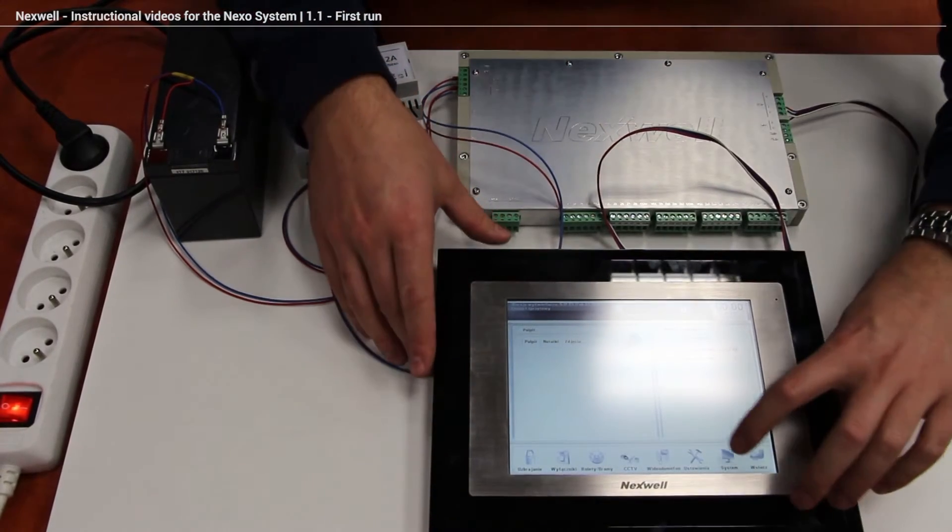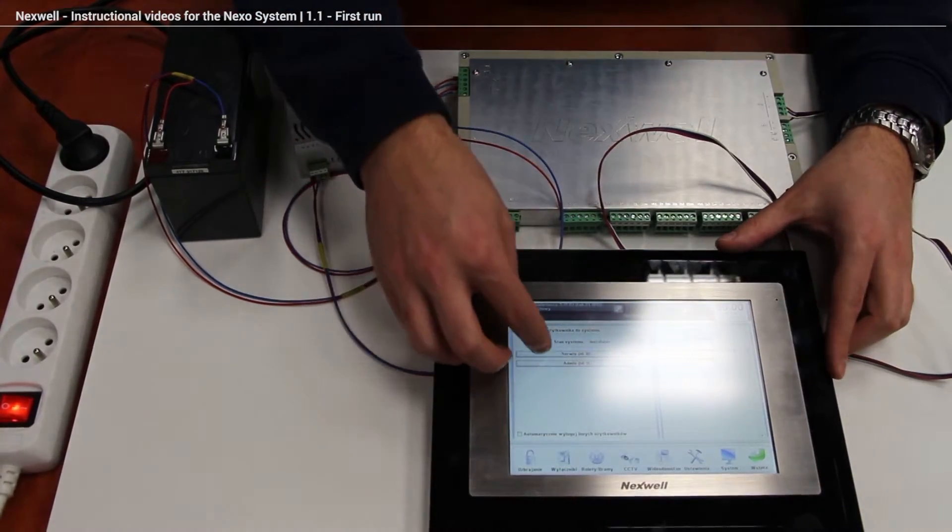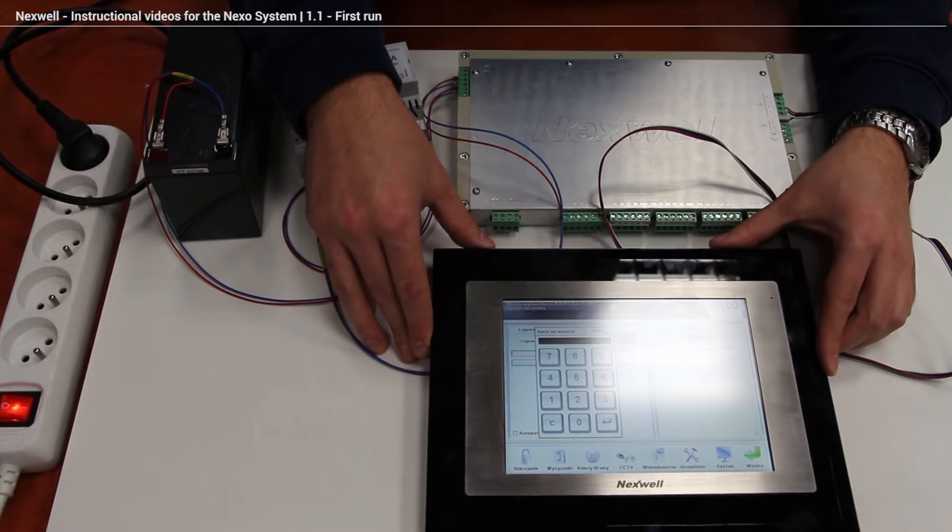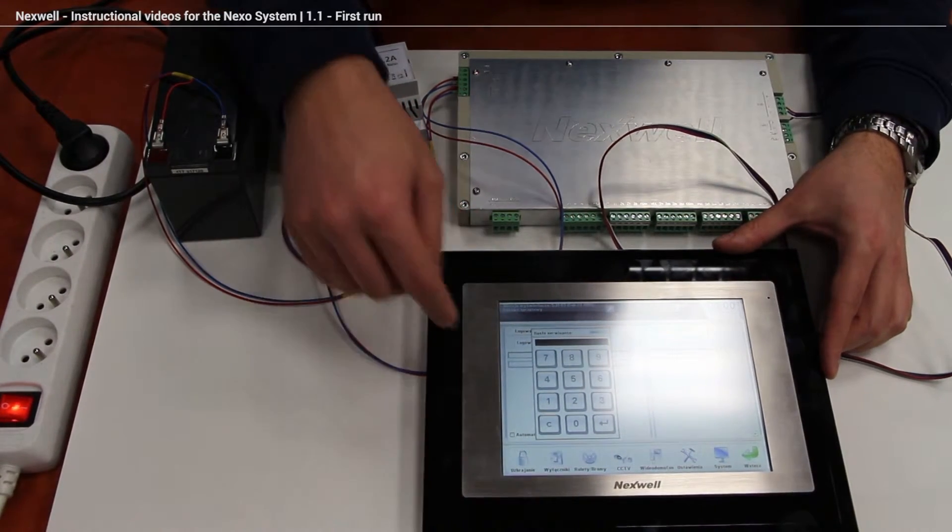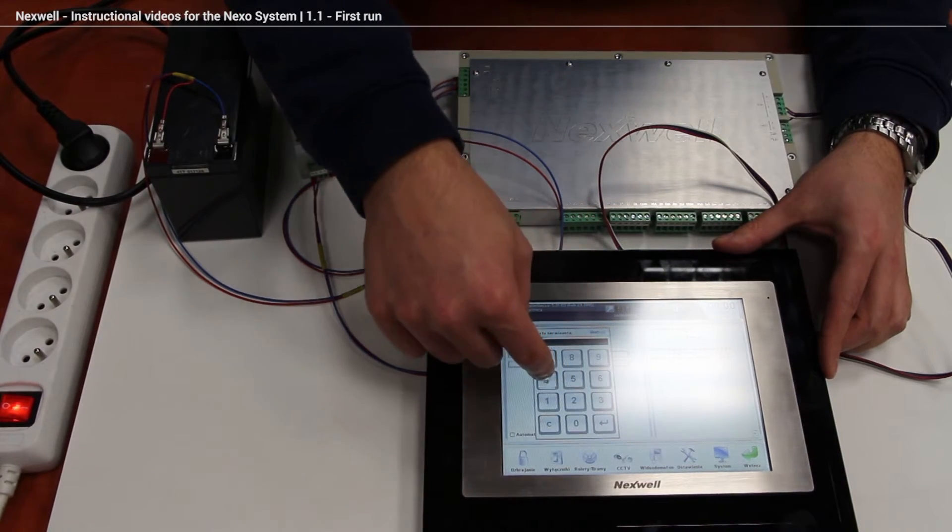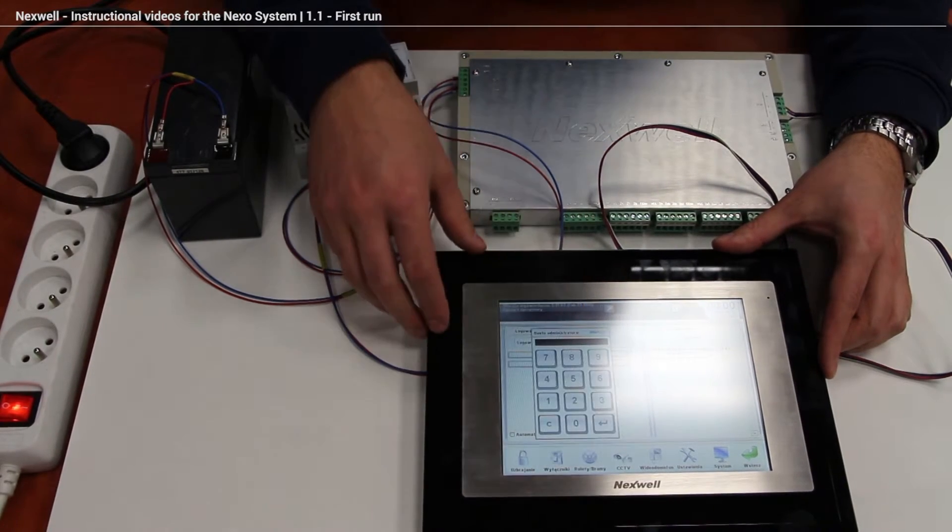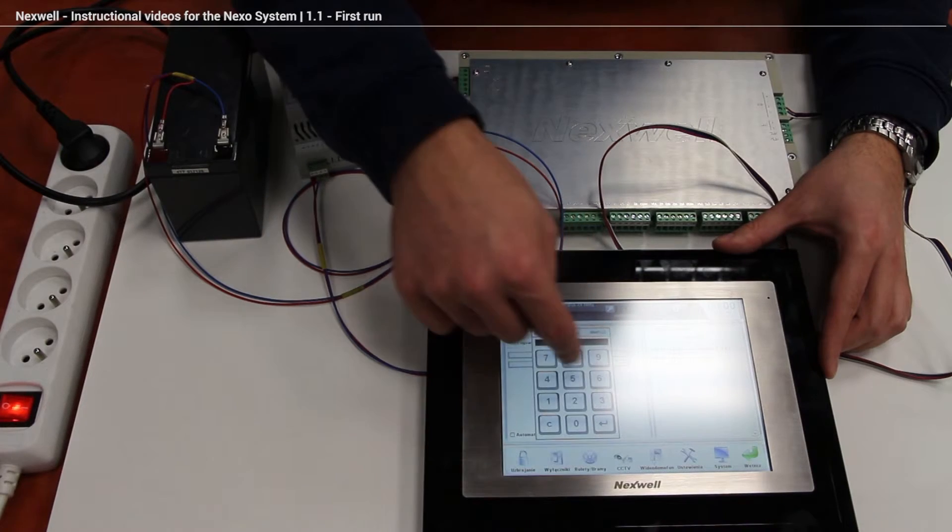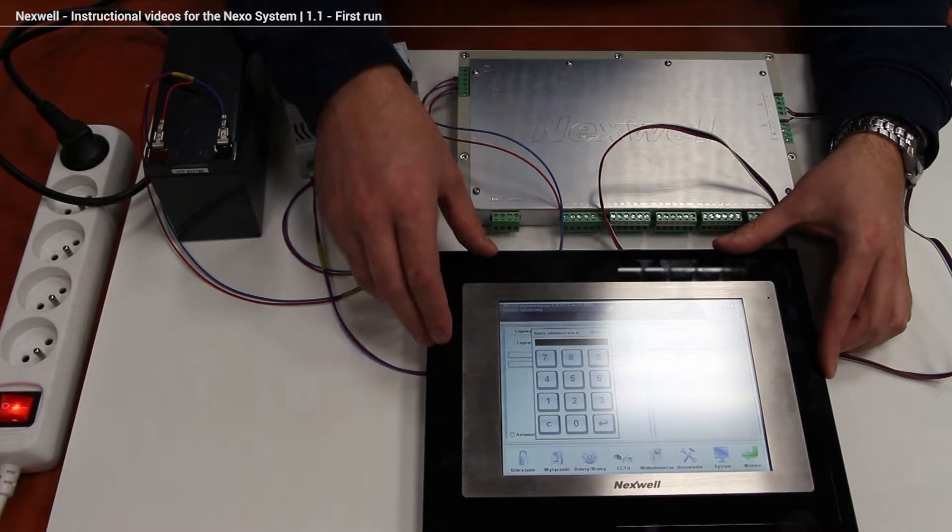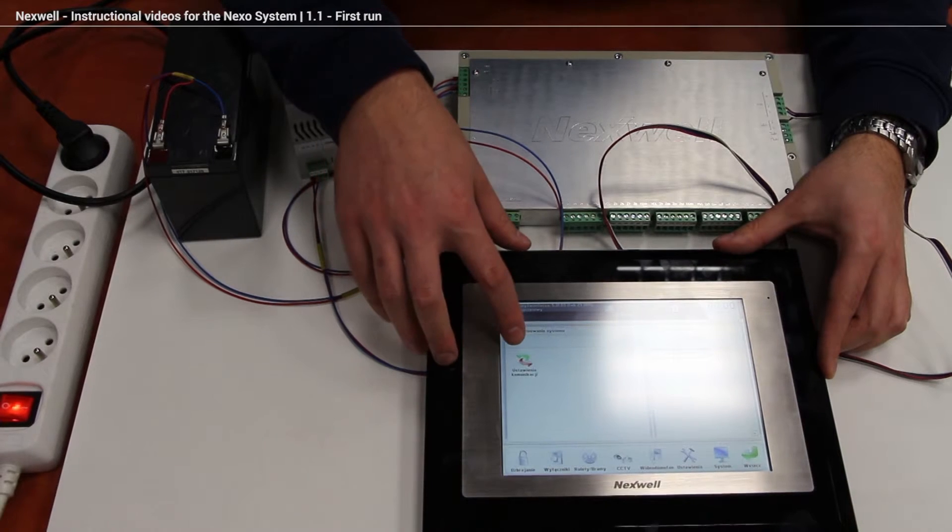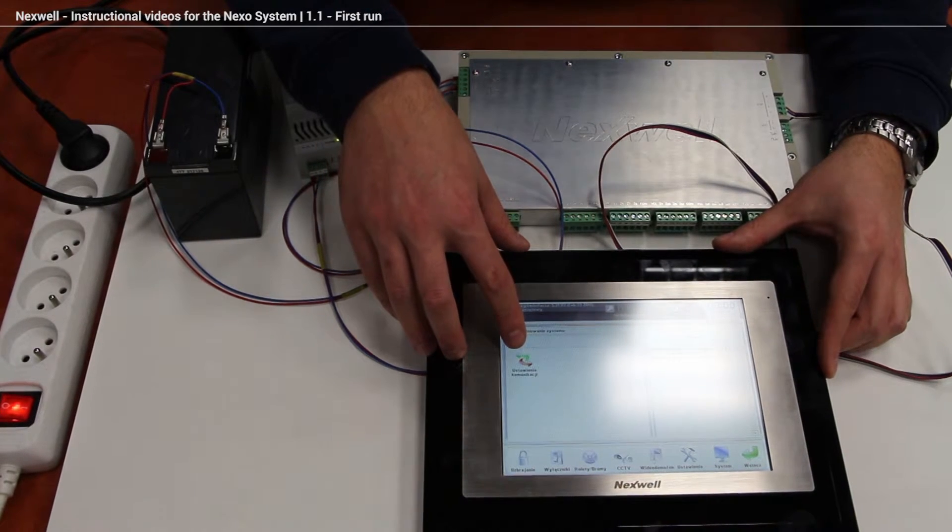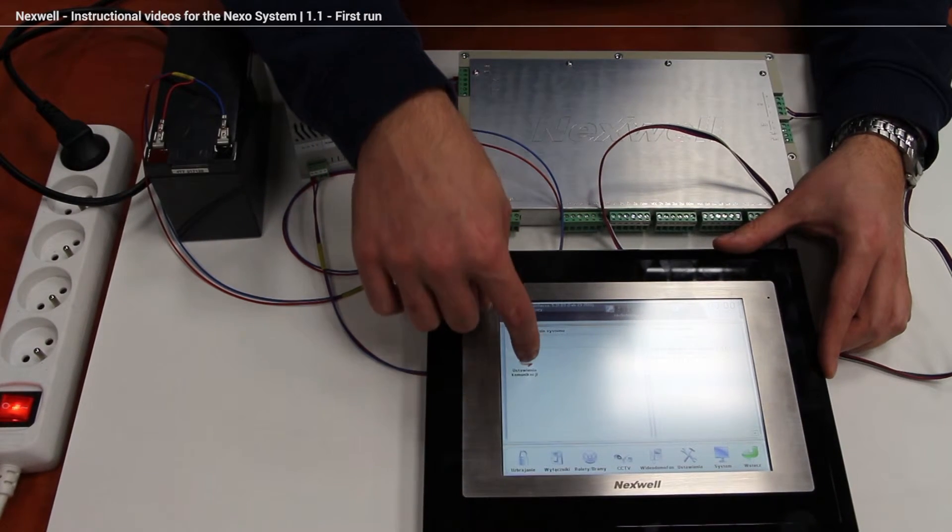To do that we have to click the system, the service mode, and we have to put some passwords. The factory password is 1234 for the service mode, enter. And 5678 for administration mode and enter. As you can see we got the communication settings icon. So we're clicking on it.